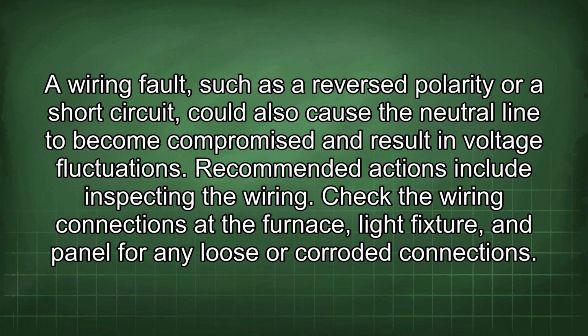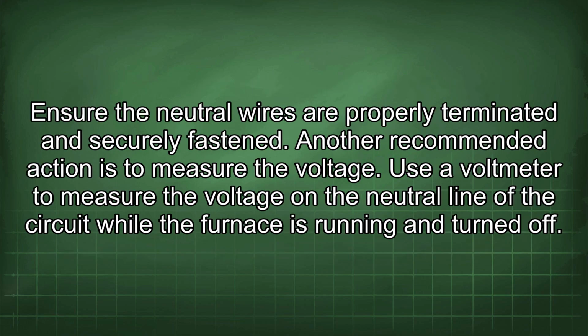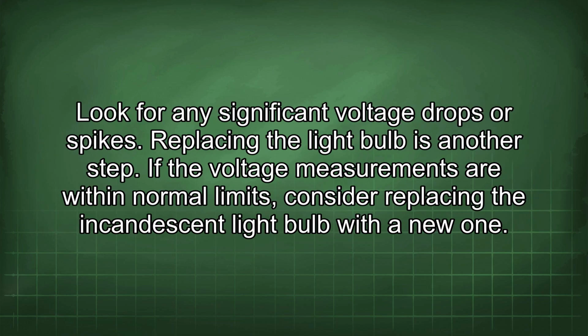Recommended actions include inspecting the wiring. Check the wiring connections at the furnace light fixture and panel for any loose or corroded connections. Ensure the neutral wires are properly terminated and securely fastened. Another recommended action is to measure the voltage. Use a voltmeter to measure the voltage on the neutral line of the circuit while the furnace is running and turned off. Look for any significant voltage drops or spikes.